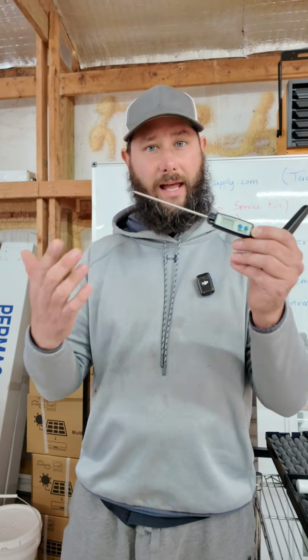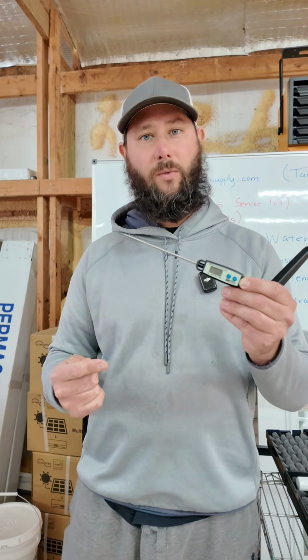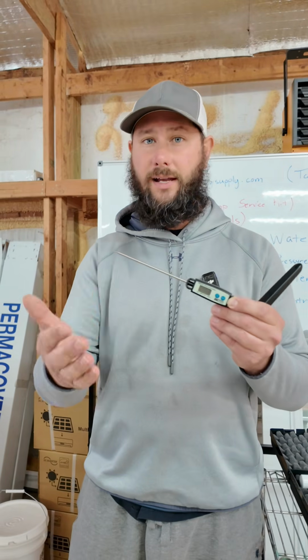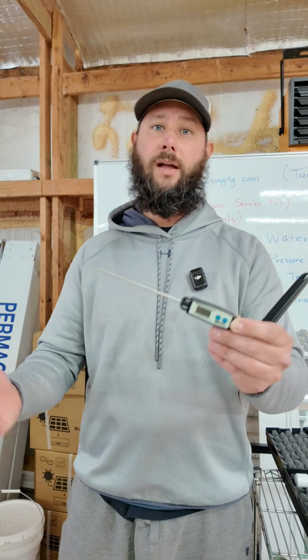Our temperature probe allows us to measure the entering and leaving water temperature at the coaxial heat exchanger so that we can calculate the heat transfer, and we can actually know if our geothermal system is moving energy.